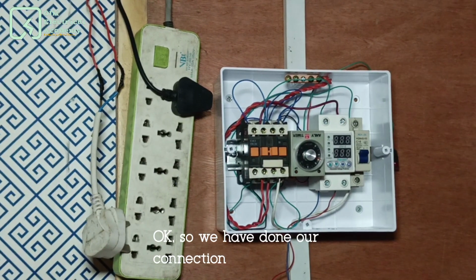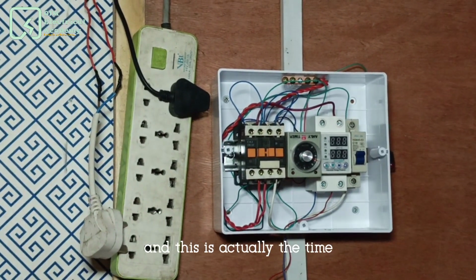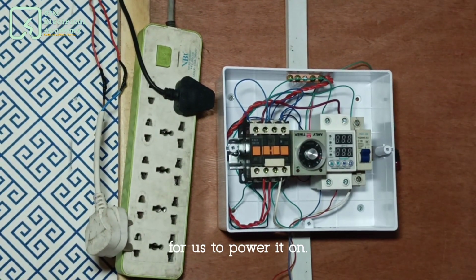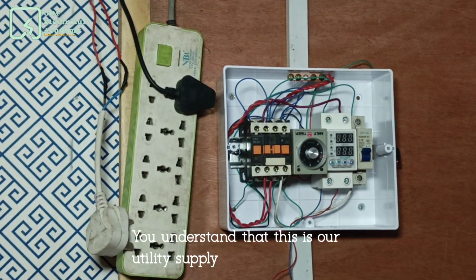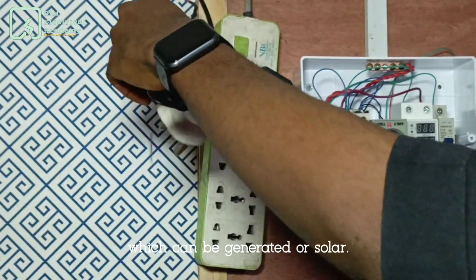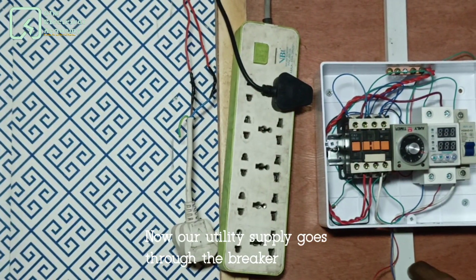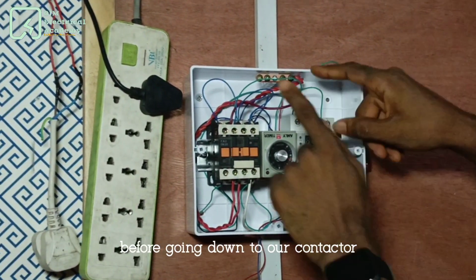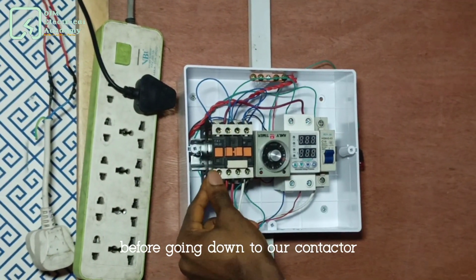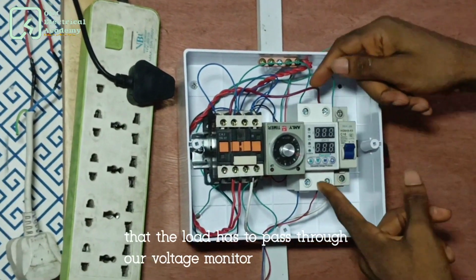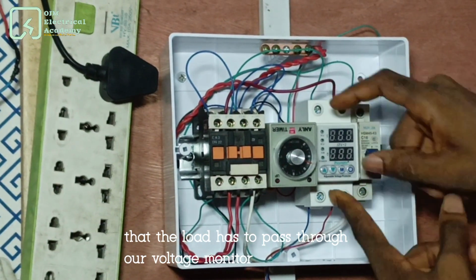Okay, so we have done our connection and this is actually the time for us to power it on. Let's recap a little bit. You understand that this is our utility supply and this is our alternate power supply, which can be generator or solar. Now our utility supply goes through the breaker before going down to our contactor, and also understand that the load has to pass through the voltage monitor before going down.